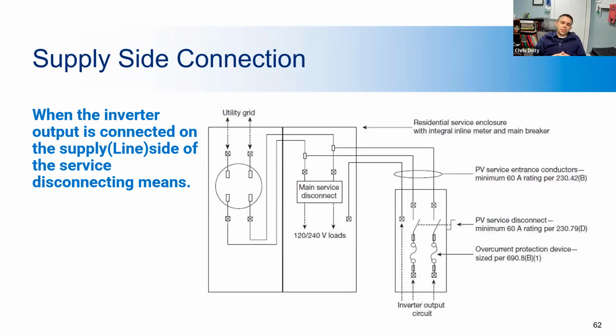So the other type of interconnection is a supply side connection. This is when the inverter output is connected to the utility side of the main service disconnect. This interconnection type is sometimes referred to as a line side connection or a line side tap. Since a supply side connection is very similar to a new service entrance, the NEC requires that the disconnect be rated for such, and it has to contain overcurrent protection, fuses or circuit breakers. At a minimum, the fault current rating should match that of the existing service equipment. And you need a 60 amp rating for entrance conductors right here, per code.